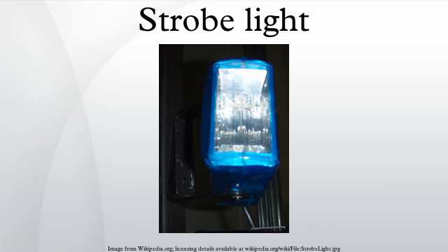Applications: stroboscopic effect. Special calibrated strobe lights, capable of flashing up to hundreds of times per second, are used in industry to stop the appearance of motion of rotating and other repetitively operating machinery and to measure, or adjust, the rotation speeds or cycle times. Since this stop is only apparent, a mark point on the rotating body will either appear to move backward or forward, or not move, depending on the frequency of the strobe flash.